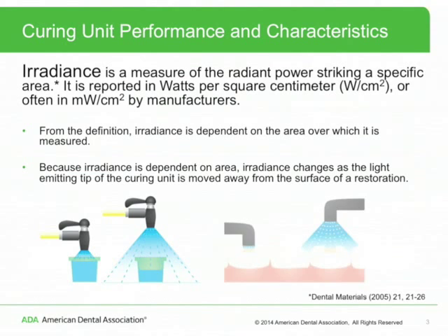When a dental curing unit is turned on, it radiates light from its emitting tip with a certain power expressed in watts. Power is a rate of energy per second; a watt can be expressed in joules per second, similar to water flow in liters per second. Like the water flowing out of the nozzle, the power does not change with distance.